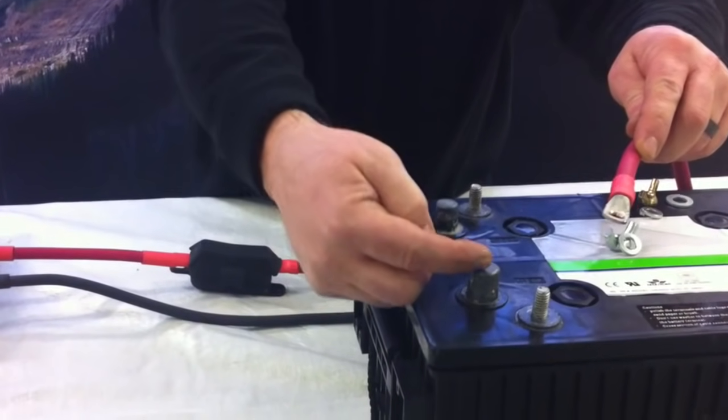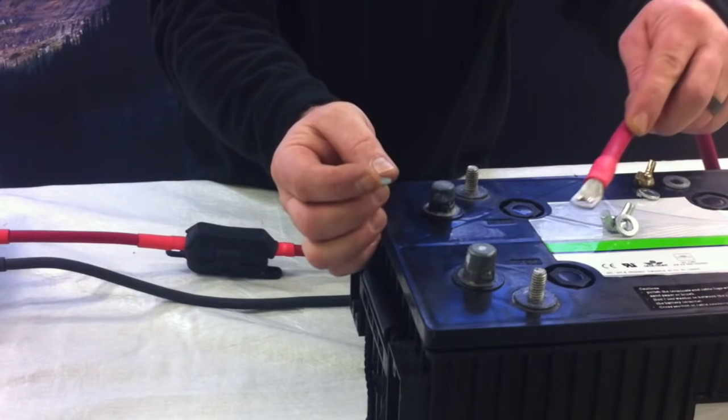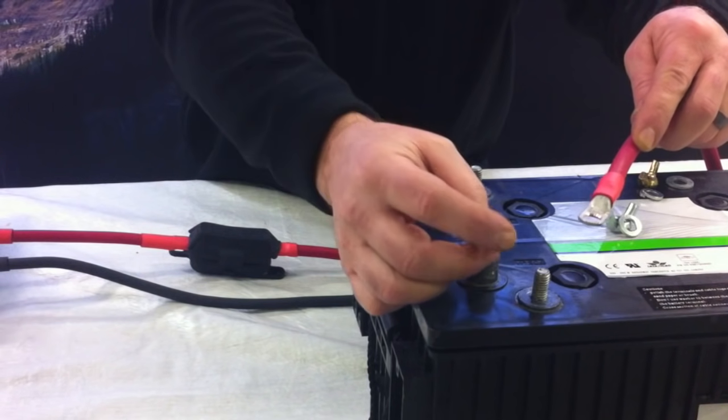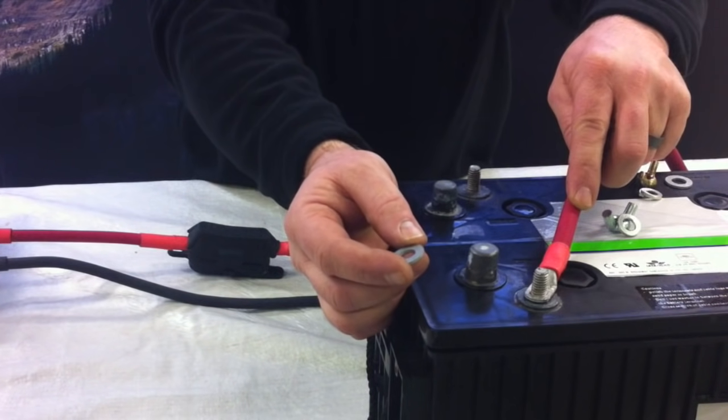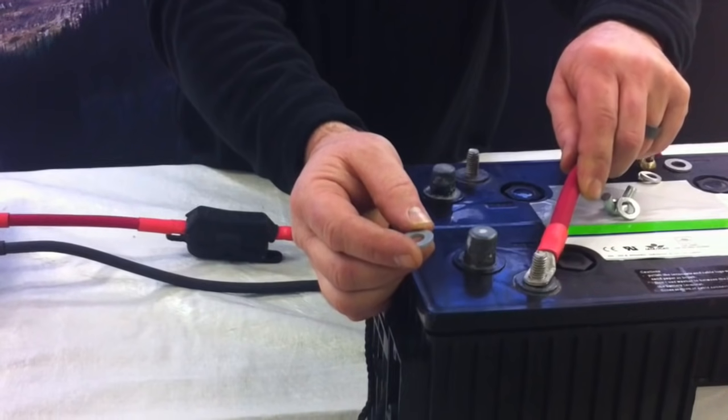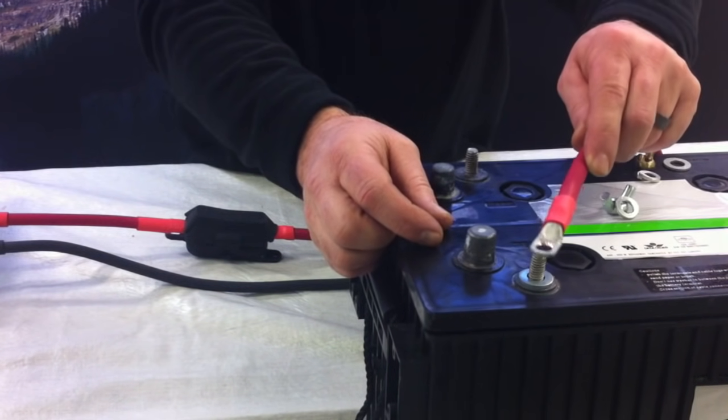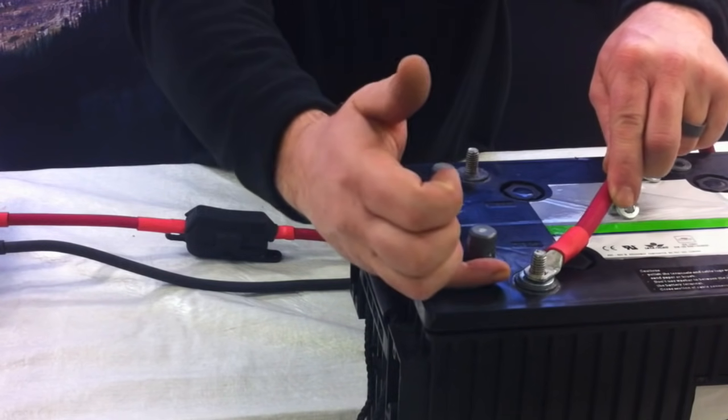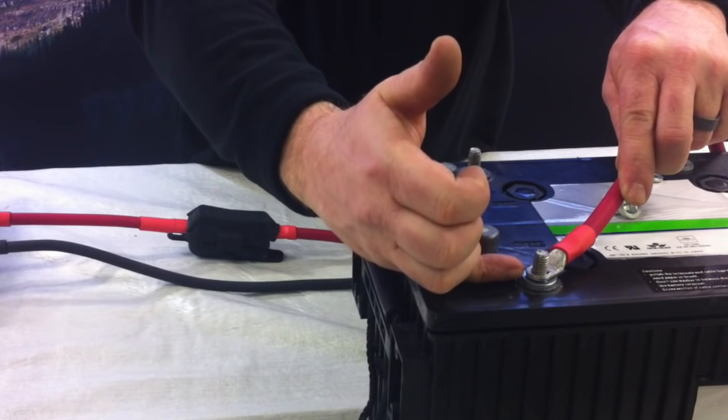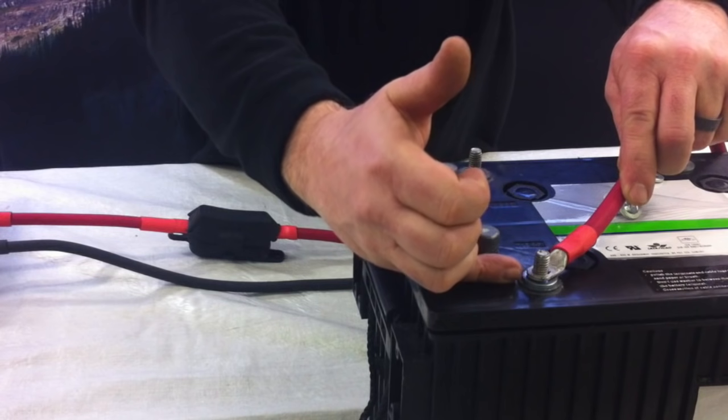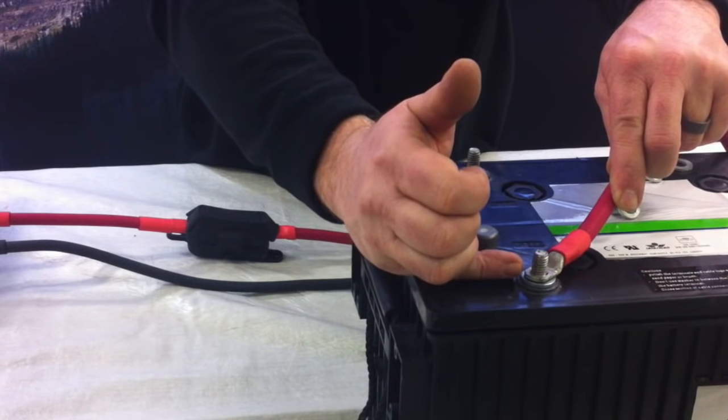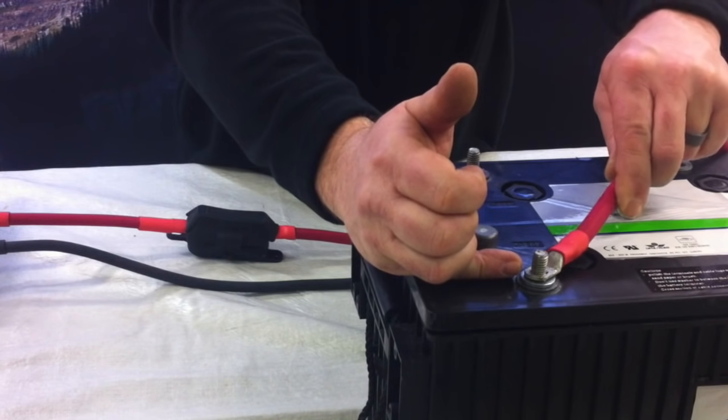So we're going to go ahead and put our positive cable on our positive terminal. One thing you want to make sure of depending on what hardware you get with a battery is that the lug goes on first and nothing goes in between the lug and the battery post. If in fact you were to put the washer down first and then the lug on top, what could happen is that the post will heat, the flat washer is going to set into the battery and you're going to end up with a loose connection and in turn you're going to end up burning the terminal in the battery.